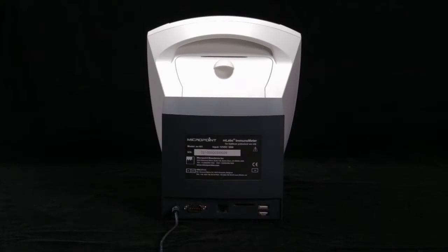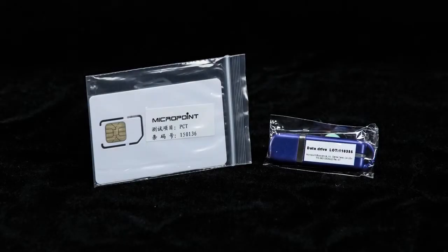Prior to running any assays, the data drive for that assay lot must be installed into the mLabs ImmunoMeter. The data drive provides lot-specific information such as the expiration date and is only required to be installed once for each lot. The mLabs ImmunoMeter can store data drives from different lots for each meter. A single lot-specific mLabs data drive is provided along with each kit of cartridges. Either USB disk or SIM card can be used.